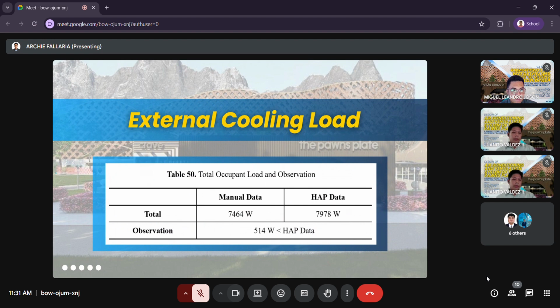Now moving on to the total occupant load and observation. This table focuses on the load from occupants derived from the heat released by 75 customers and 15 employees occupying the restaurant during peak hours. The manual calculation estimated a total occupant load of 7,464 watts using standard heat gain values per person based on the activity levels. In comparison, the HAP software output was slightly higher at 7,978 watts, showing a difference of 514 watts.